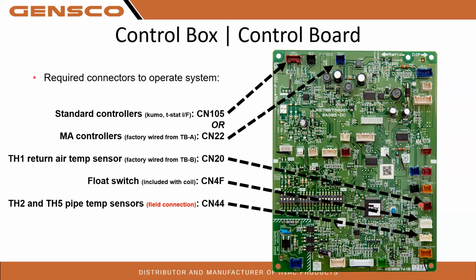Your return temperature thermistor right here, that one is also factory wired into the control board, and we'll get into that a little bit more in a little bit. So you don't have to worry about anything on there. These two plugs right here, this is your float switch for your CN4F. So that condensate safety switch that comes in the kit that does not plug into your 24-volt controls is going to plug in right here. So in the kit comes a little pigtail with a plug-in. So you'll wire nut your condensate safety switch into that, and it'll plug into right here. Your coil temp thermistors, TH2 and TH5 pipe thermistors that are wired onto the coil, they're going to plug right here into CN44.